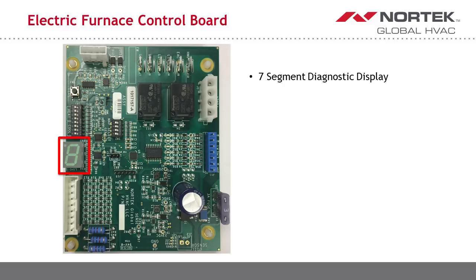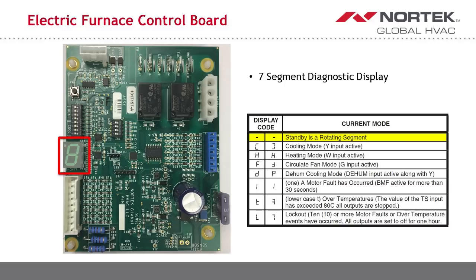The display will always show one of the following images, which signal if the unit is in standby, cooling, heating, fan circulation speed, dehumidification mode, or if a motor fault has occurred. There is also an over-temperature fault that causes the unit to completely shut down, and a lockout when more than 10 faults have occurred. The lockout lasts for 1 hour. You will notice there are 2 display images on the table. This is because the lights will be rotated 180 degrees depending on the orientation of the furnace. This simplification will allow contractors to install the equipment more quickly, service the unit in the field correctly and more easily, and provide better comfort to the homeowner.